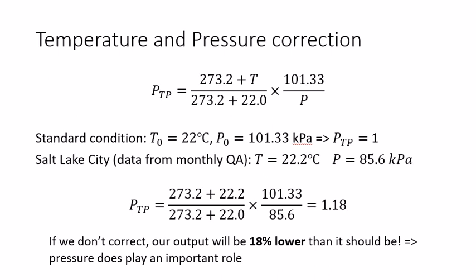So under this example, our PTP is calculated as 1.18, which is 18% higher than unity. So if we forget to apply the PTP correction and we use unity, we use 1 as the PTP factor, our measured output will be 18% lower than it should be.